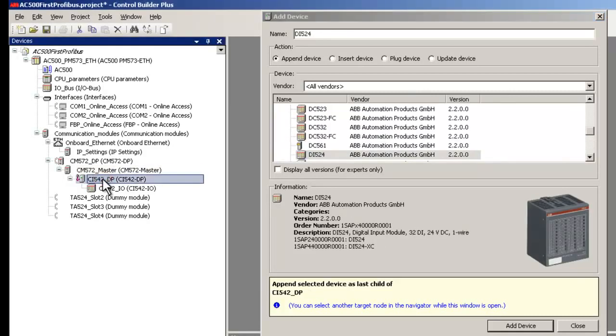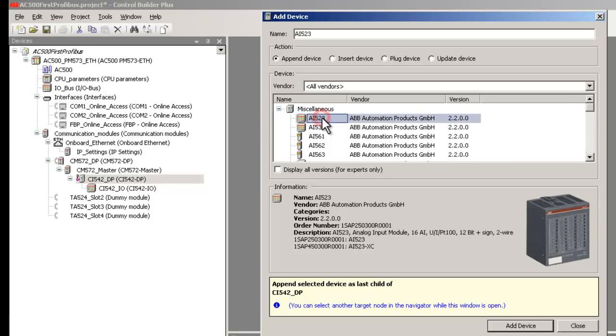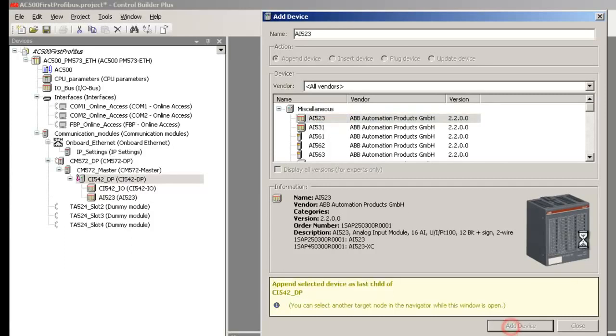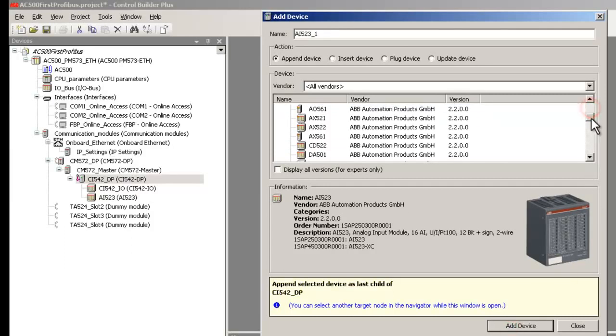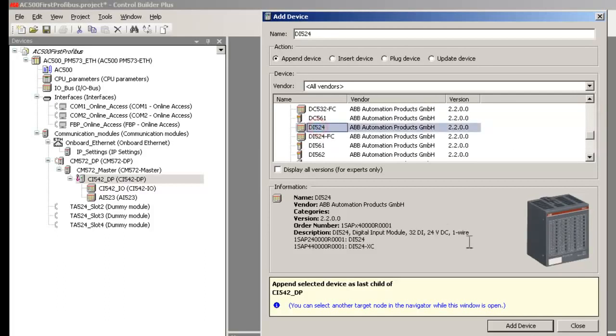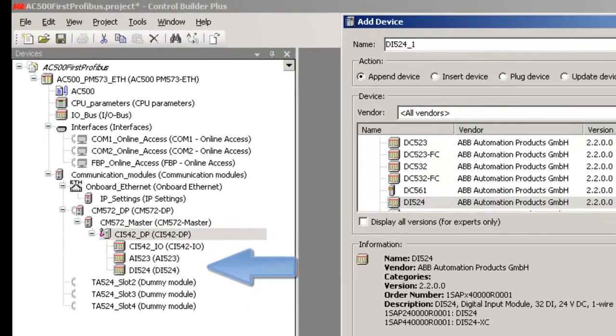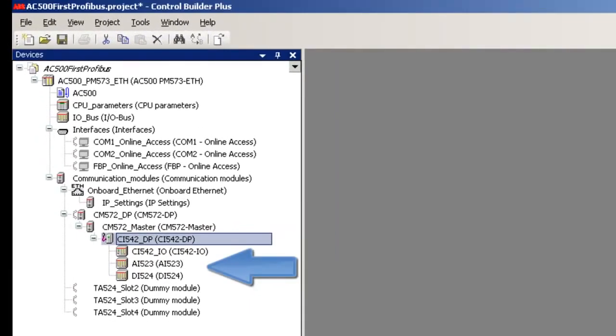Now, to add the I/O modules on the slave station, right-click on CI542DP module in the configuration tree. And with the Add Device option, add all the I/O modules. Do keep in mind the order in which they are physically mounted on the I/O rack.